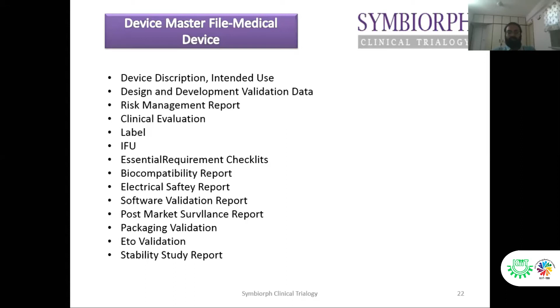This is the basic requirement for medical devices. Now, what will be the requirement for IVD? Suppose you are a manufacturer of in vitro diagnostic medical devices, so what will be the requirement of the device master file? Again, you have to have a brief description of your device, intended use, and classification. Again, all the validation data with respect to design and development, risk management, and performance evaluation. Here, you have to do a performance evaluation. Performance evaluation is similar to clinical evaluation, but in IVD we use the word performance evaluation. Here also you have to do a pilot and pivotal performance evaluation with the help of patients.